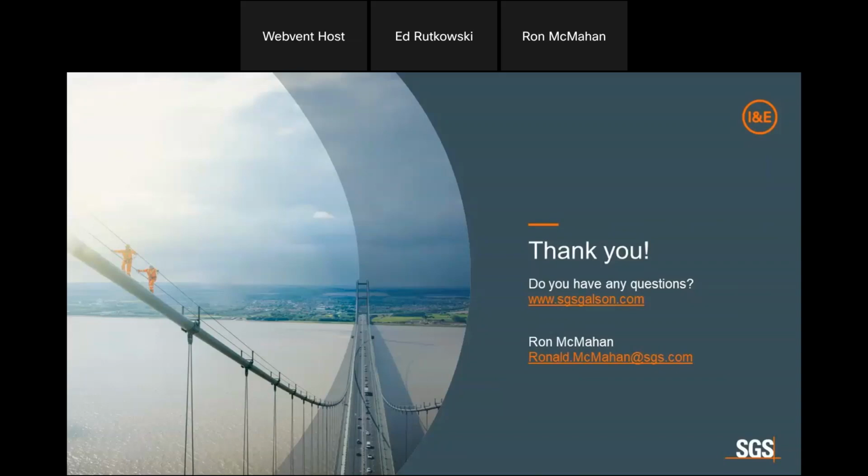Okay, thanks, Ron. Chris has two questions. I'm going to ask them both right now. What does the calibration adapter look like for the EcoMeasure units? And what is the flow rate used for the calibration gas to the cal adapter? So the cal adapter was basically just tubing to a nipple that goes into the side of the instrument. Then we used different things that would seal the front part of the unit all the way down to where the inlet was to the particle sensor. The flow rate was 0.4 to 0.5 liters per minute. If we used more or less, it would potentially take a lot longer and starve out. If there was more, then we would see a potential pressurization, and then the readings would be off.